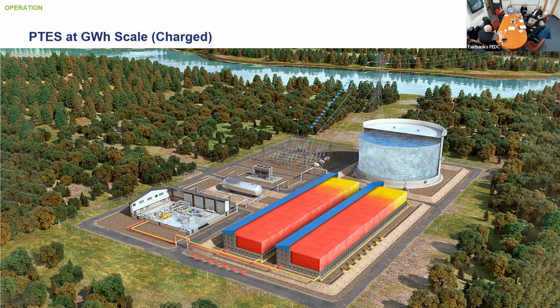All of these closed loop power cycles and heat pump cycles have a high pressure side and a low pressure side. On our low pressure side, we're subcritical, so the CO2 acts like a more traditional fluid - it's liquid and vapor. We take advantage of that because during the liquid to vapor transition, it's doing that at constant temperature, just the same as water freezing at constant temperature. So it's a good match there.